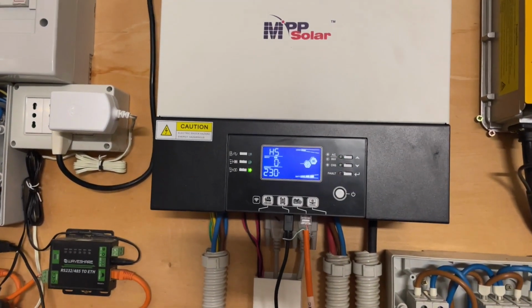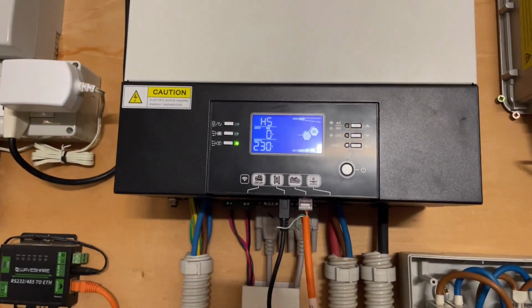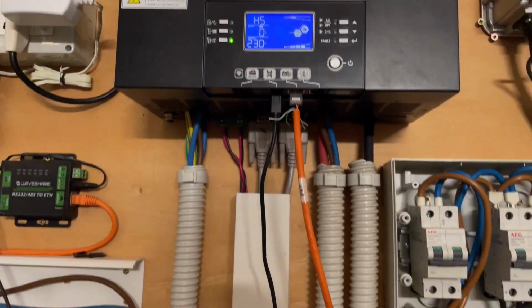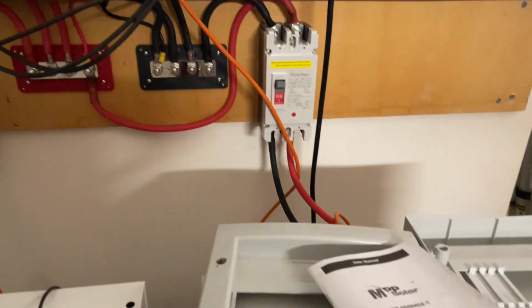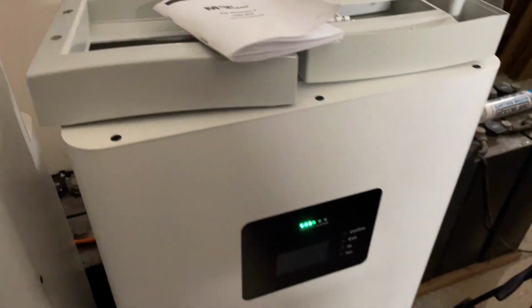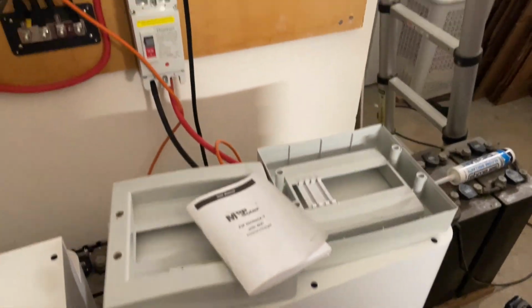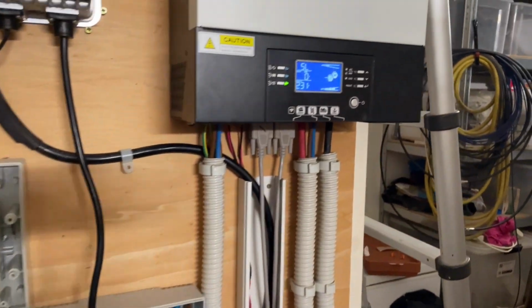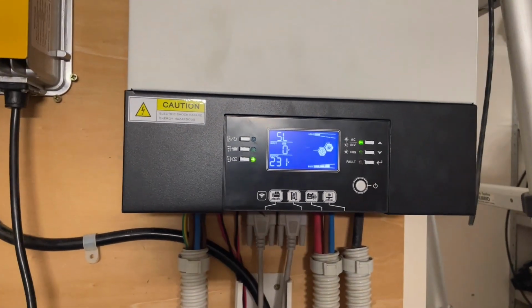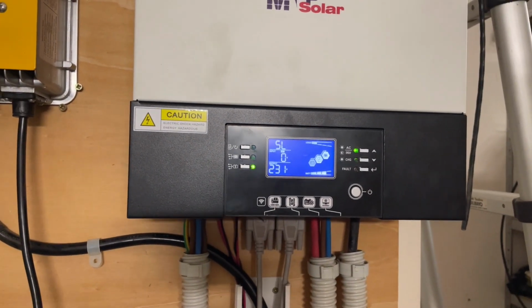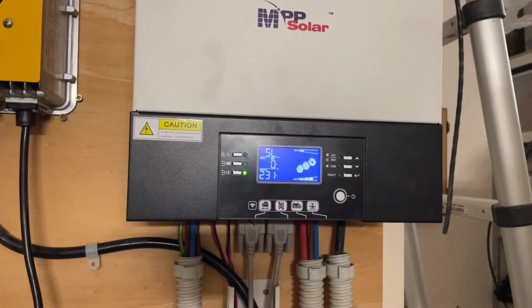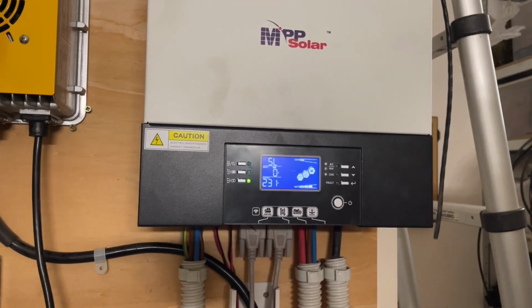Okay, so the master inverter has got the BMS cable plugged into it, which then plugs into the master set plus battery. The slave inverter, however, has no BMS cable set in it, so it would run for 5 minutes and then come up with a failure code of 61.